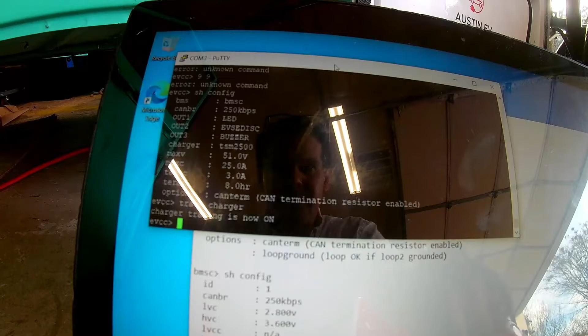This stage of charge is called the absorption charge stage, where voltage is held constant and current falls in a fairly linear fashion over time from max current to 0. Since the charge controller seems set to turn off when the current falls below 3 amps, we still have a bit further to go to finish our charging here.